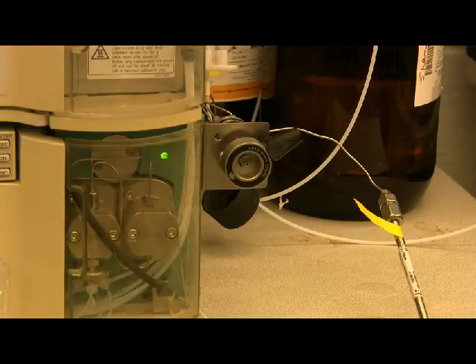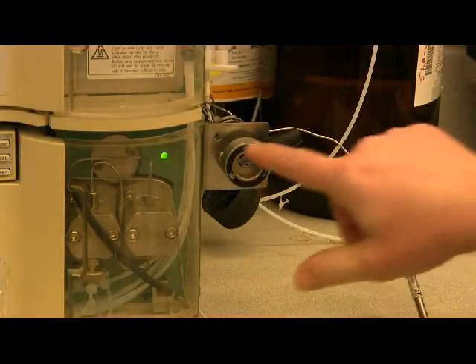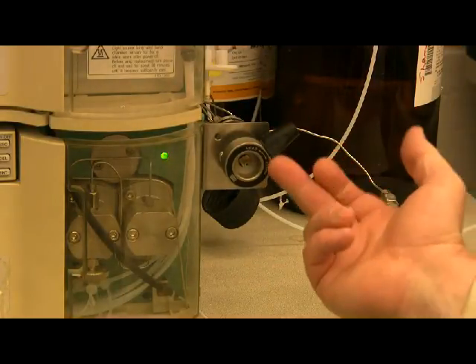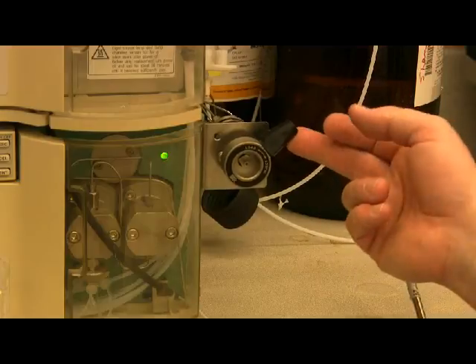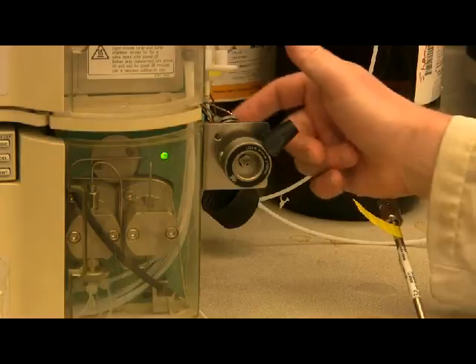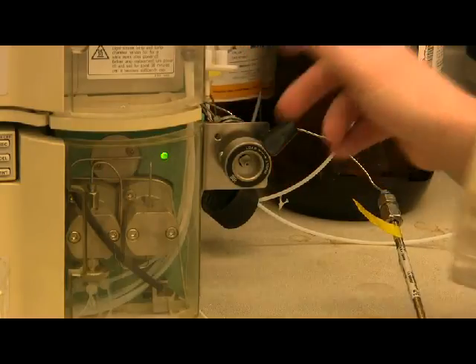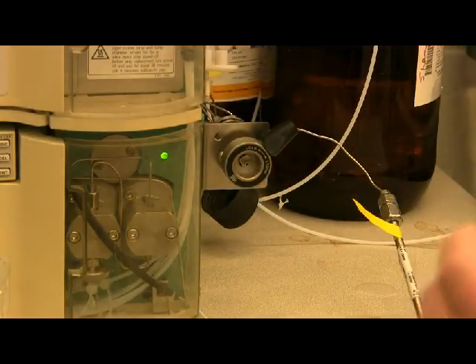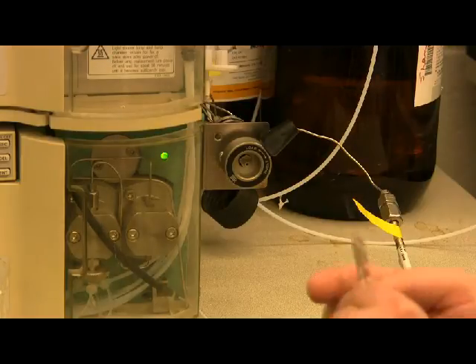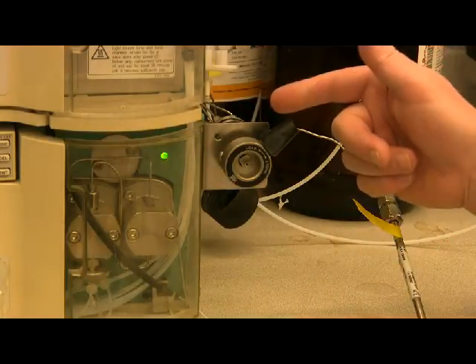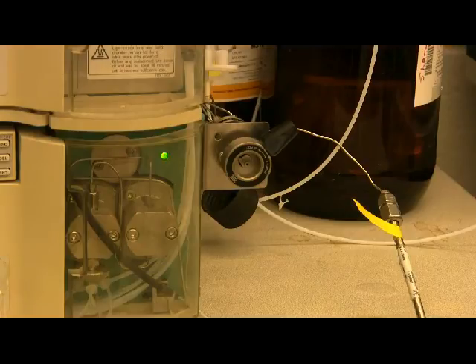So next we have to inject our analyte. This is the injection port. You can see that it's in the load position. It's up. It has two positions, load and inject. Inject is down. There's a 20 microliter injection loop. So even if you're using a 100 microliter syringe to inject, you cannot overfill the sample loop. It's only going to hold 20 microliters.